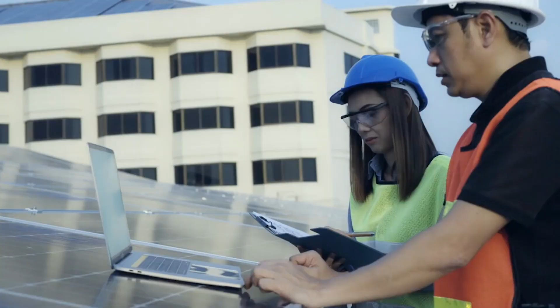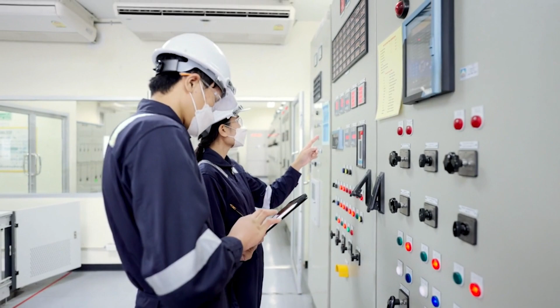Early in projects, the smaller details may not seem as important. You'll hear, 'we can figure that out later.' But these small items quickly compound to a lot of small things to determine in the field. When 10 or 20% of the design details are missing because of this approach, this becomes a significant effort to figure out during critical path on-site commissioning.